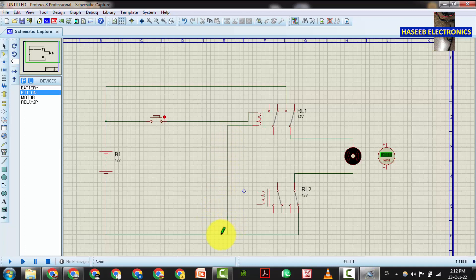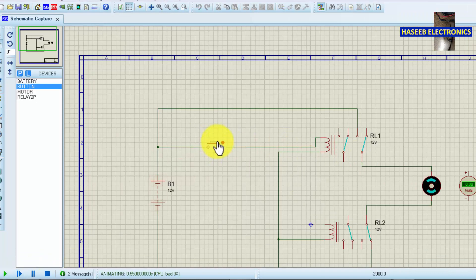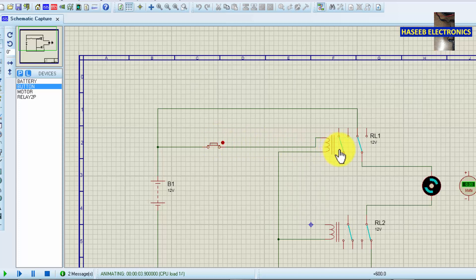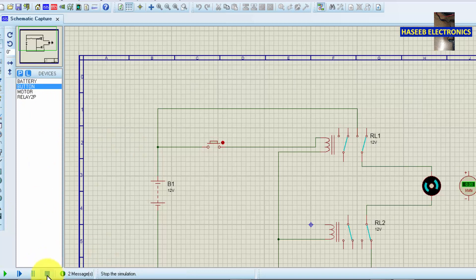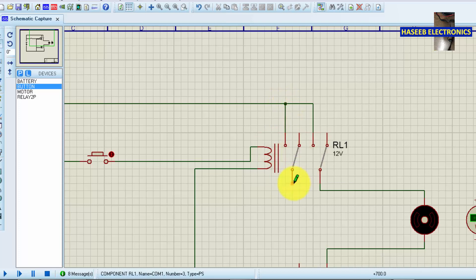Now we will design this circuit logically. This end of the relay will go to ground. The second relay will also connect one end to ground. If we turn on this switch and simulate, the relay turns on, but when we release the switch it turns off because it is a push button, not a toggle switch. So we need to make an interlock. When this relay turns on, we will take the positive voltage supplied here and feed it back to the relay coil to latch it.